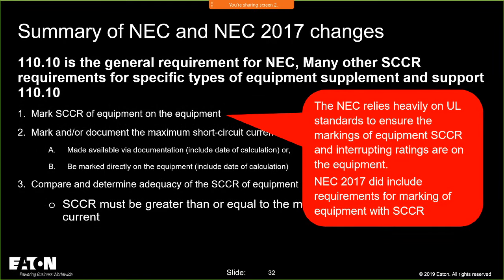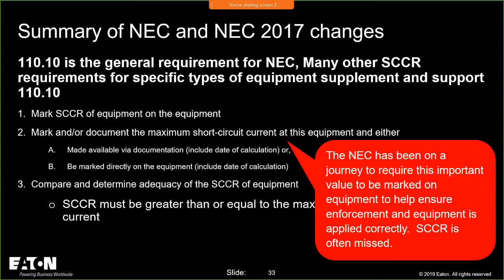So the NEC relies, in my opinion, heavily on the listing and labeling requirements of products that we install in the field. For the most part, most of that equipment is going to be required by the listing to be marked. I'm going to educate you a little bit on how panel boards and switchboards are marked differently. But when you're looking at the 17 cycle and the 2020 cycle, there's a mix. Some of them require that you field mark the available short circuit current. Some of them require that you just have documentation available. And the reason one is marking and one is not is because of two different code panels. One code panel thought it was important to field mark. The other code making panel thought it was more important just to have it available as documentation, so they didn't go to the field marking. We're going to talk about that as well.